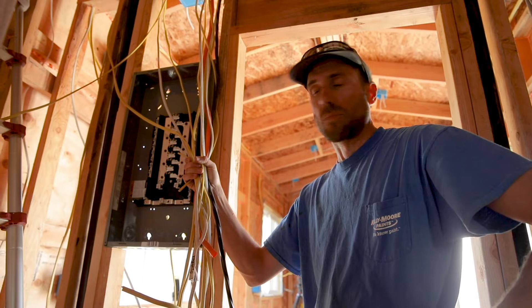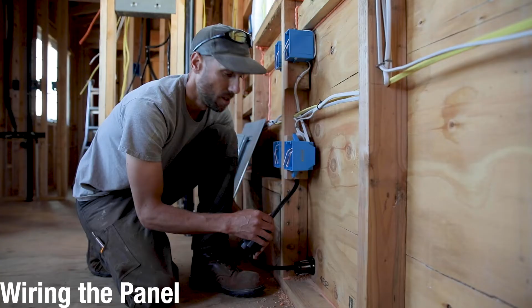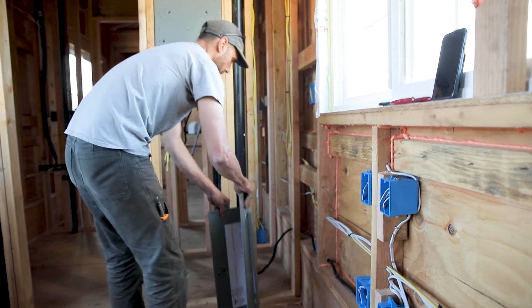So we still got a couple circuits to go, but you can see every single one of these wires is a different circuit that's going to connect to a circuit breaker on our main panel here. So here's where our power's coming in, and this will just close over there, and we're going to use some plumber's tape to really secure this good so it's going to stay in place. And then we'll tighten up this wire a little bit more. And you can see how that's running across here and up to our panel. And this is where the power enters the panel.